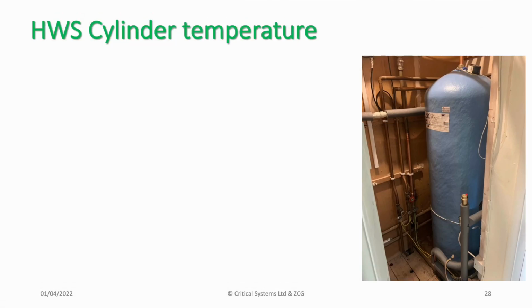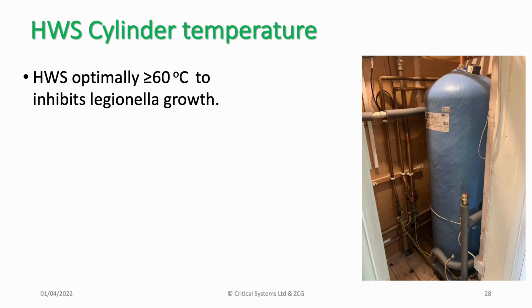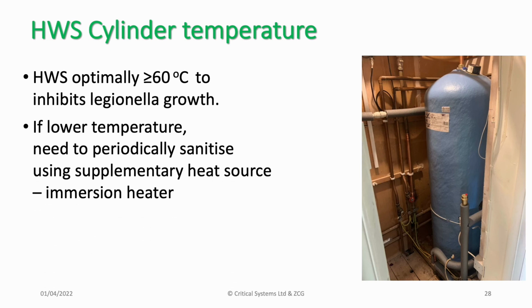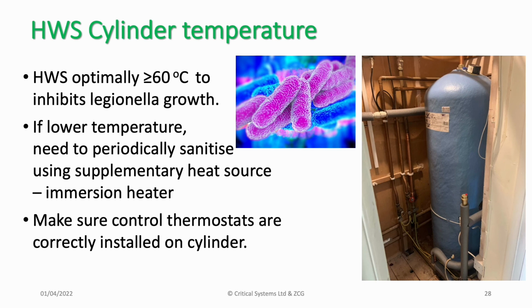We also need to consider the hot water cylinder, the domestic hot water temperature. Now, optimally, this should be greater than 60 degrees C to inhibit Legionella growth. Now, if I'm using a lower temperature heat source from, say, a heat pump system, then I would need to periodically heat this hot water cylinder to a much higher temperature to sanitize it, using probably an electrical immersion heater fed from mains power or photovoltaic source. You need to make sure in such a system that all the temperature detectors are at the right location and that they are calibrated and working correctly.